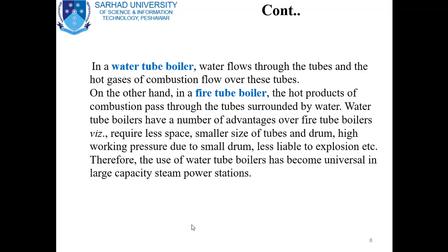On the other hand, in a fire tube boiler, the hot products of combustion pass through the tubes and the water surrounds them. Water tube boilers have a number of advantages over fire tube boilers: they require less space, smaller size of tubes and drum, and have high working pressure due to the small drum, and are less liable to explosion.